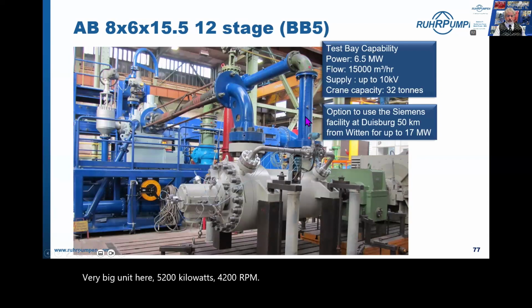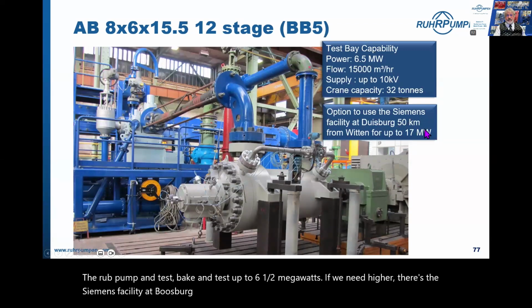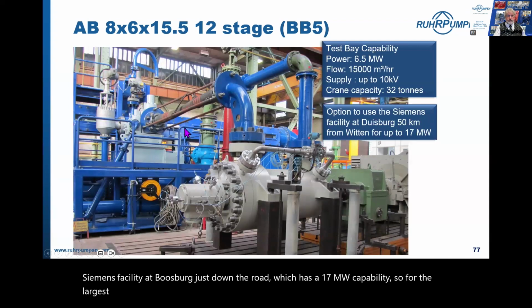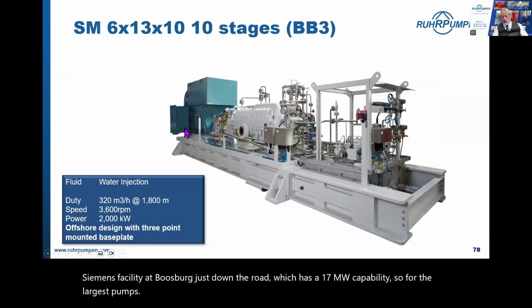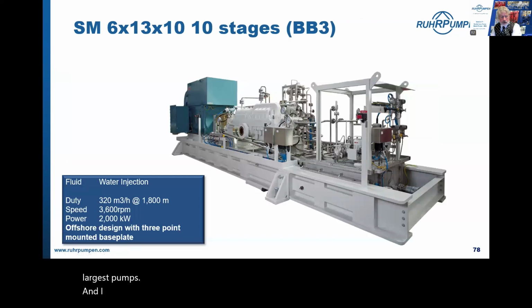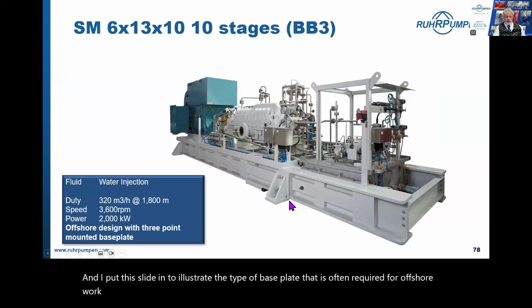The Ruhrpumpen test bay can test up to 6.5 megawatts. If we need higher, there's the Siemens facility at Duisburg just down the road, which has a 17 megawatt capability, so for the largest pumps. And I put this slide in to illustrate the type of base plate that is often required for offshore work, with a 3-point mount base plate.